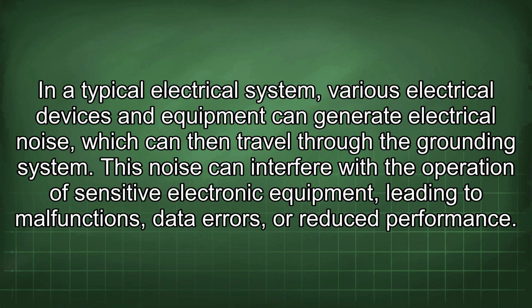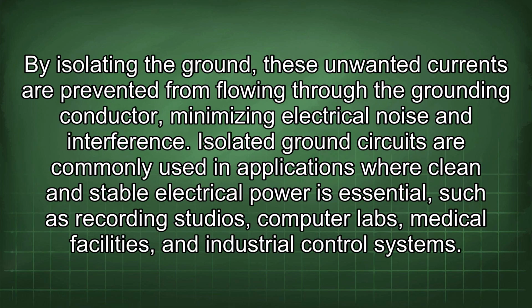In a typical electrical system, various electrical devices and equipment can generate electrical noise, which can then travel through the grounding system. This noise can interfere with the operation of sensitive electronic equipment, leading to malfunctions, data errors, or reduced performance.